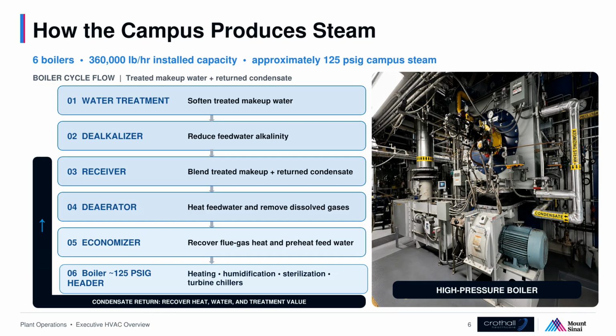Six boilers provide 360,000 pounds per hour of installed capacity and feed the campus steam header at roughly 125 psi. Steam supports heating, humidification, and sterile processing. After steam gives up its heat, recovering the condensate returns hot, treated water to the cycle and reduces make-up water, chemical use, and fuel demand.